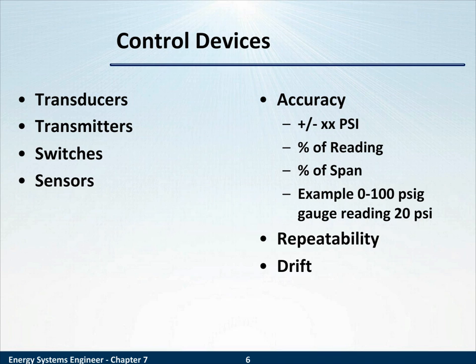Repeatability says, if you take that measurement 10 times, how close will those 10 measurements be together? And drift says, if you take that measurement 10 times over a course of time, maybe 10 days, will that value drift up or down, or neither?